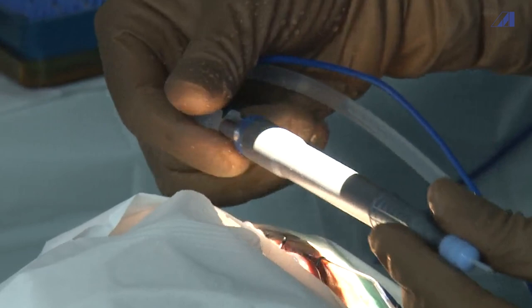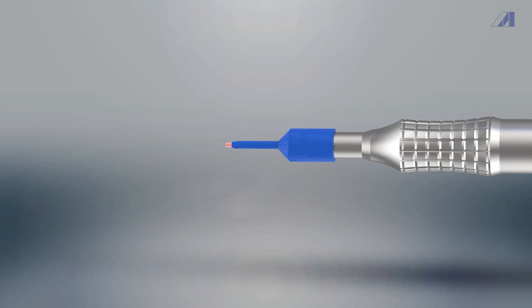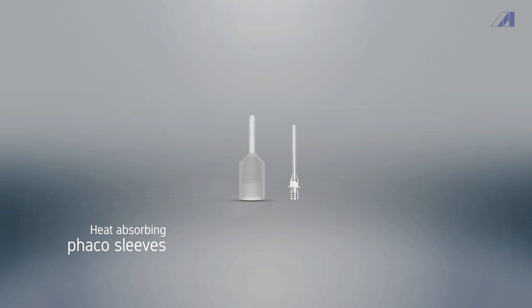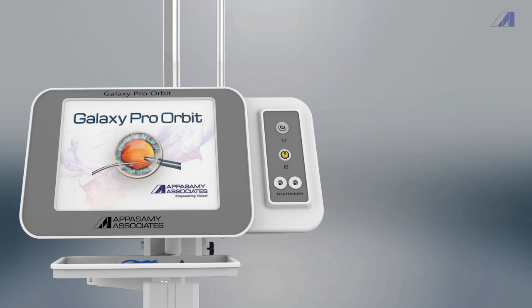During the phacoemulsification procedure, there is a chance of heat emission making the phaco tip hotter and leading to corneal burns. To avoid this, phaco sleeves are provided.